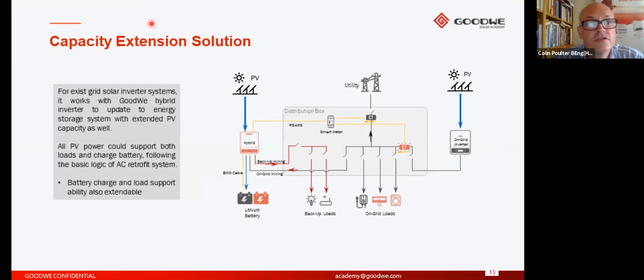So we're going to look at another solution here, referred to as a capacity extension solution. This means that within a property you can add a hybrid inverter to an existing standard on-grid inverter. Because we have a smart meter, it monitors the power flow back to the grid or from the grid, monitoring the AC excess power generated by both the hybrid inverter and the on-grid inverter. When it detects that excess is being developed, the batteries will charge from both the output of the hybrid inverter and the on-grid inverter. This behaves a bit like an AC retrofit system since it detects the AC power.